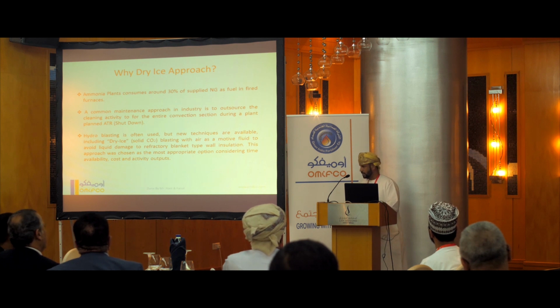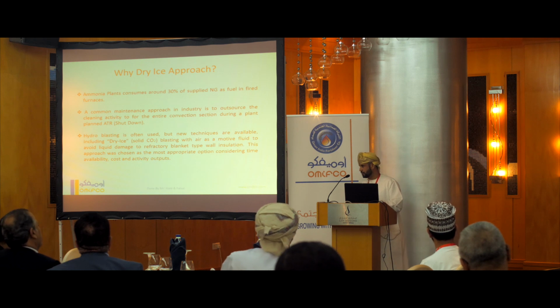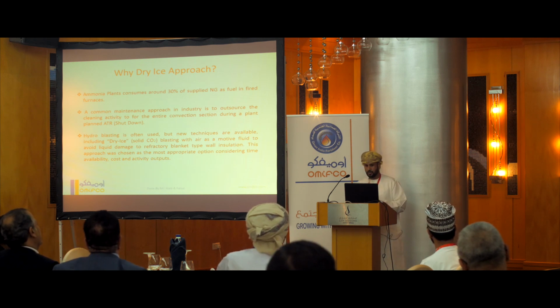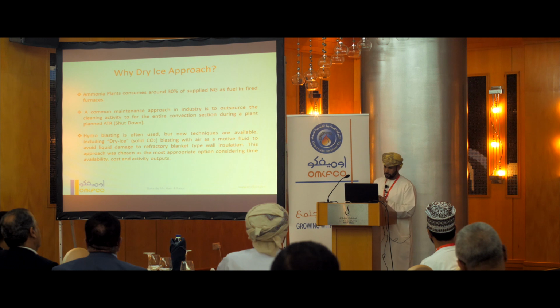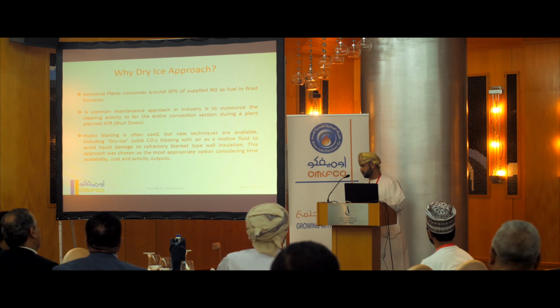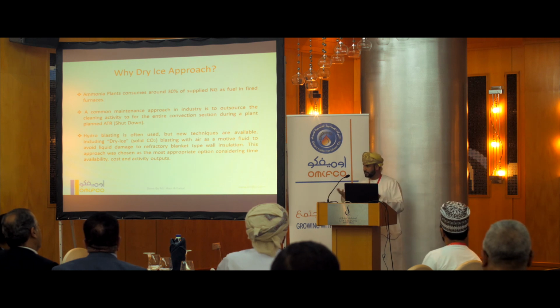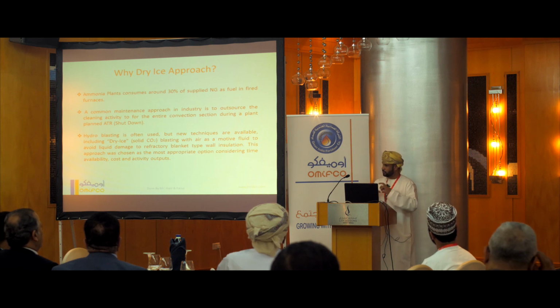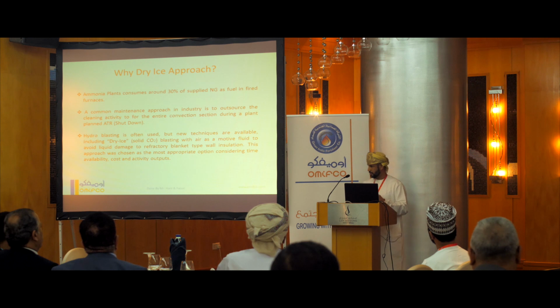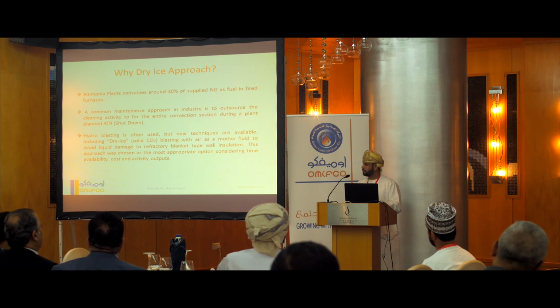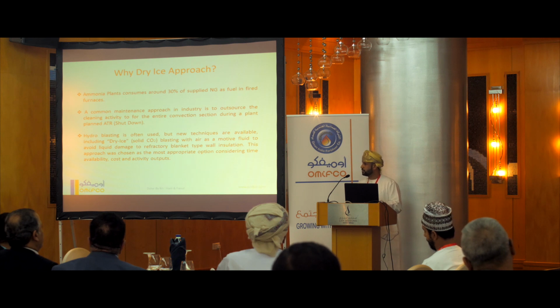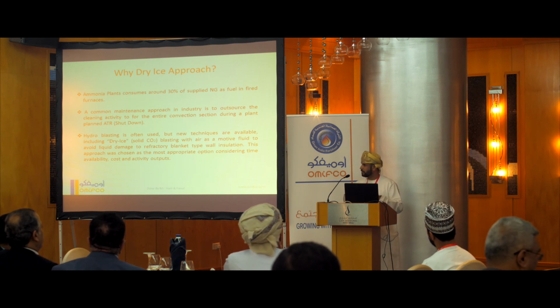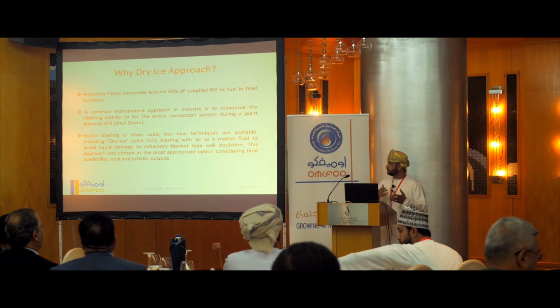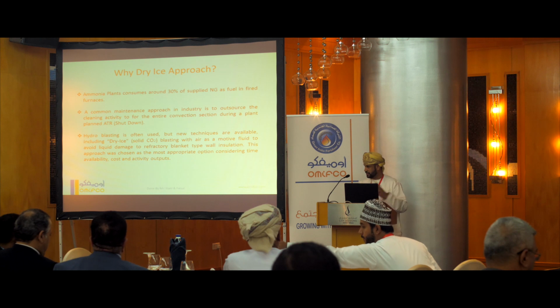Hydroblasting was often used before, we have used it, but the performance was not as good as dry ice. Techniques available include dry ice blasting. It avoids liquid damage of the refractory, because normally we are using water, and there is refractory on the side and the bottom of the waste heat section, so it can be damaged. Sometimes it is damaged by the water when we use the water jet to remove the dirt. But this technique is improving, and even where there is not that much dirt, it can be removed by vacuum. Very easy to remove. It does not affect the waste heat section that much.